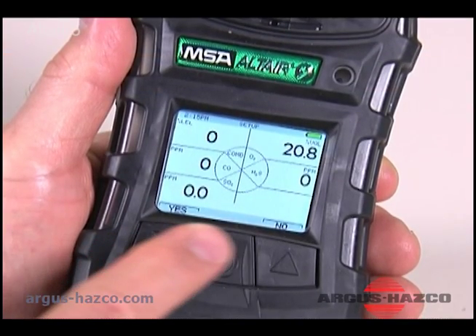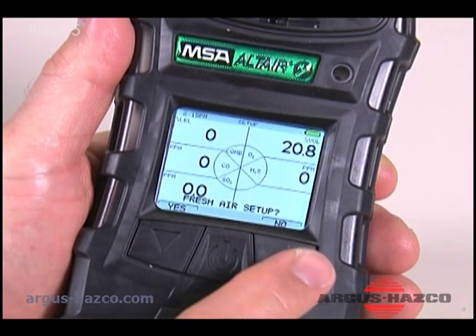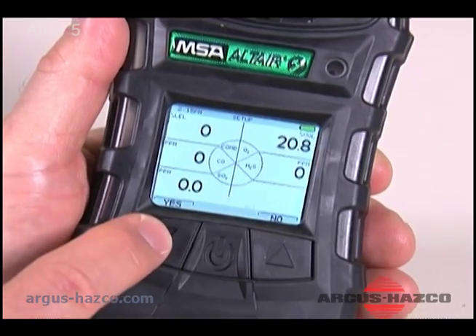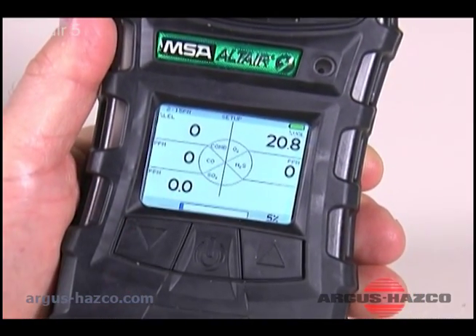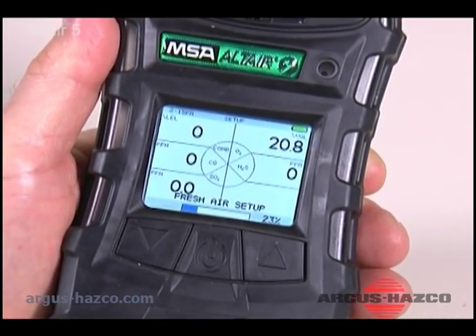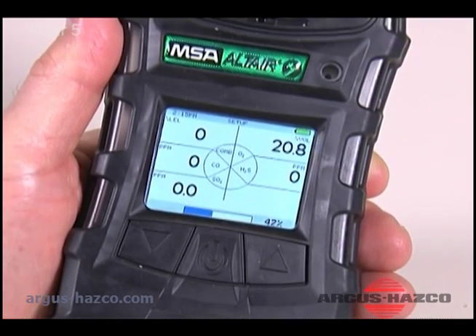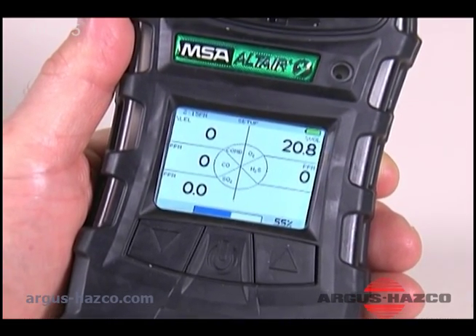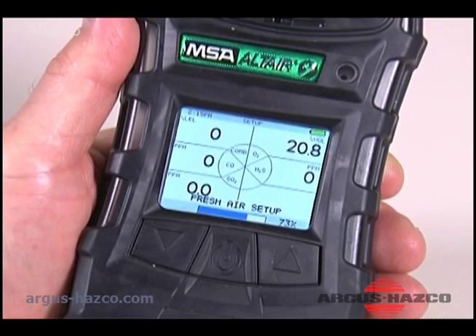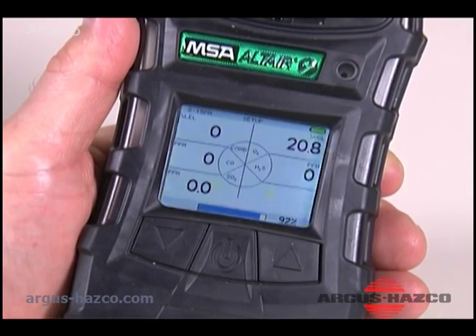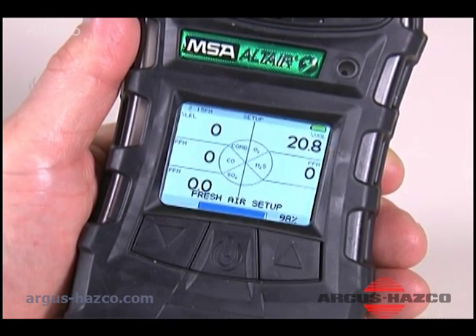To skip the fresh air setup and go directly into measurement mode, press the up arrow. To perform a fresh air setup, press the down arrow button. Within preset limits, fresh air setup sets all sensors to 0. If the instrument passes the fresh air setup, it automatically enters measurement mode and is ready to use.